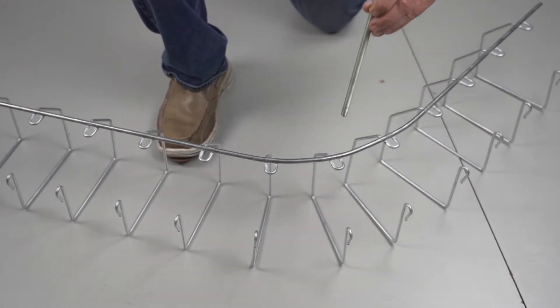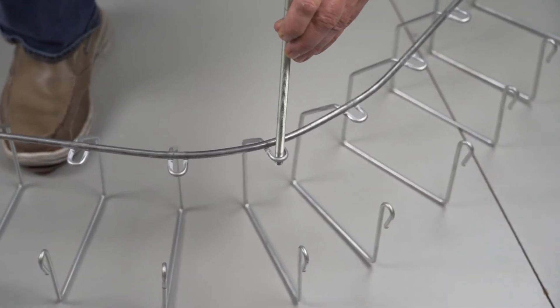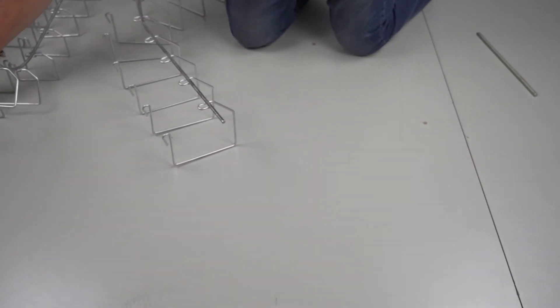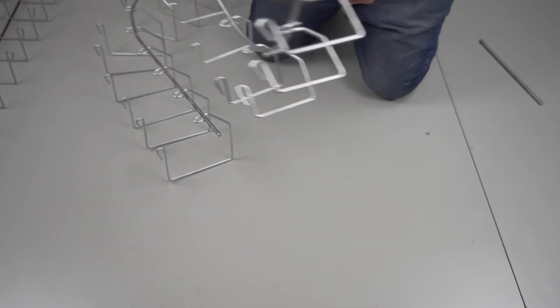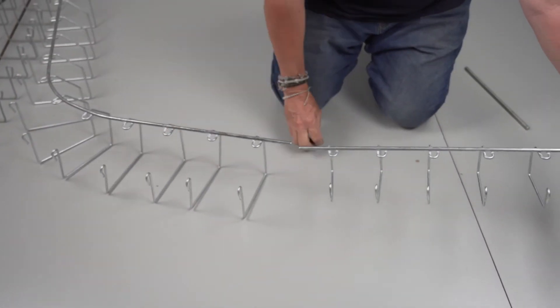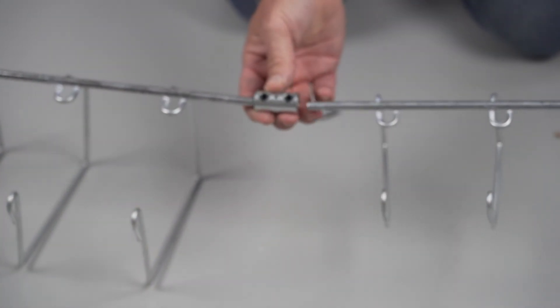And again when we bolted on the threaded rod, that loop on the top is what we're going to use to mount the threaded rod directly to the tray. Now we can also join our sections of tray together. Very easy. It's a barrel bolt.